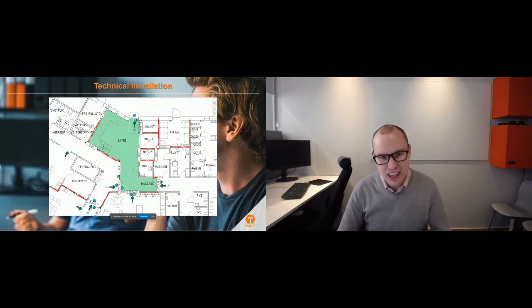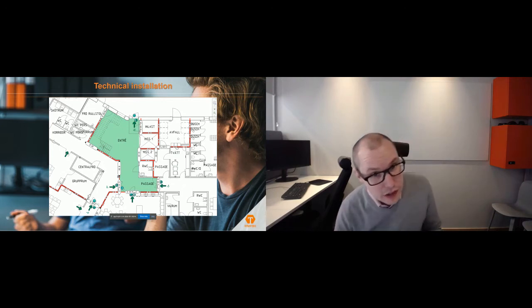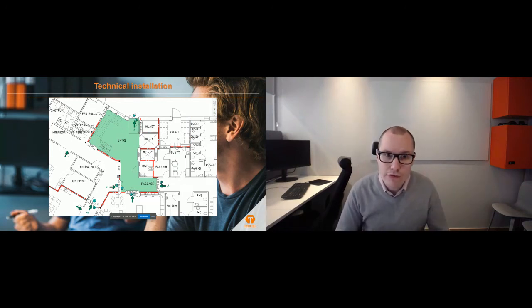We have the technical installation. This is the green one that you can see here. It's the traditional green for evacuation route. And this, of course, works for several different stakeholders in the evacuation plan, showcasing that this is the route you are going to need to evacuate. This is the strategy.